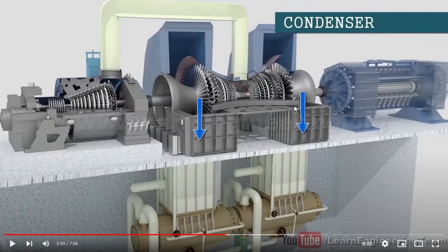Okay, so, but the condenser, right, like we talked about. Oh, okay. I don't have that in here, but we'll go over that hot reheat again, right? So if you hit that part, it goes where it's coming from the boiler, right? You've got that high pressure steam that comes through this little high pressure section of the turbine, and then it goes out of there and goes back up into the boiler, right? And it gets heated up again, and then it comes back down, and now it's heated up to like 1,040 pounds and like 1,050 degrees or something like that.